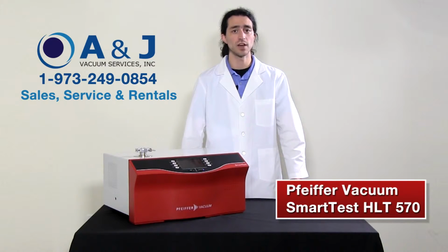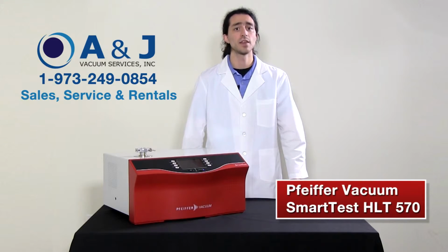The Pfeiffer HLT 570 has 2 leak detection methods, the vacuum method and the sniffing method. In the vacuum method test, gas is blown against the wall of the evacuated sample from the atmosphere side. It enters the sample at the leaks and is fed to the leak detector. In the sniffing method, the test gas escaping from leaks in the sample into the atmosphere is detected. To detect a leak, the sniffing probe is applied to the points of the sample under helium overpressure which are suspected of leaking. An increased leak rate value indicates an increased concentration of helium and therefore a leak.